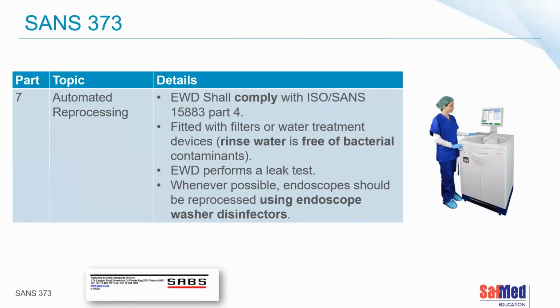We know that automated reprocessing is the way to go. Automated reprocessing is validatable, verifiable. I've taken a few pointers out of the SANS standard for now, including that the endoscope washer disinfector shall comply with ISO SANS 15883 part 4, that the washer should be fitted with filters or at least a water treatment process so the final rinse water is free of bacterial contaminants, and that the endoscope washer disinfector must perform a leak test, which is also part of 15883. Wherever possible, all endoscopes should be reprocessed using an endoscope washer disinfector and not just a manual process.